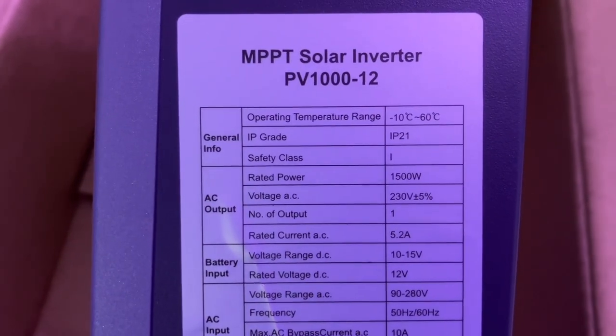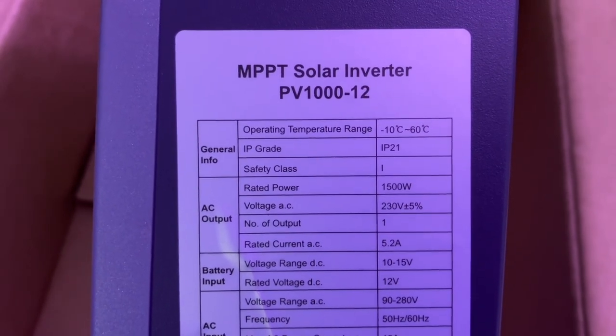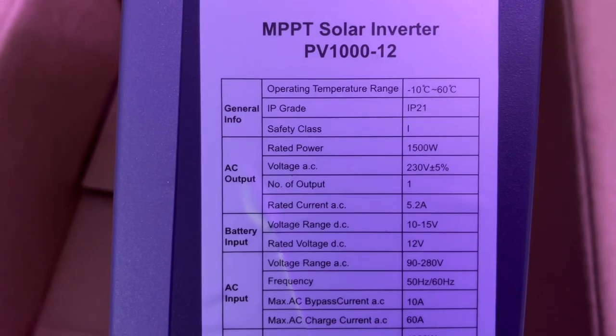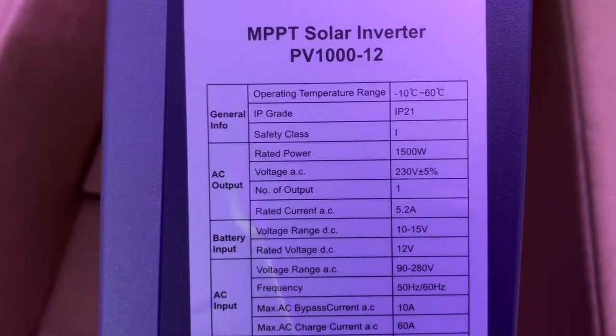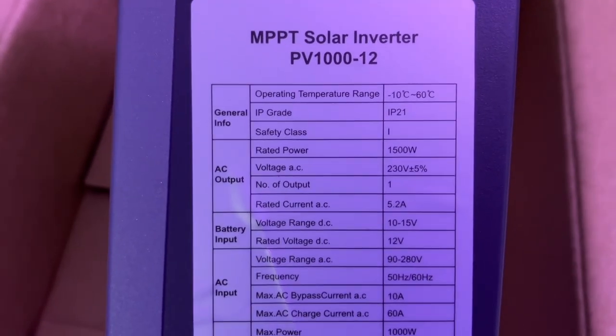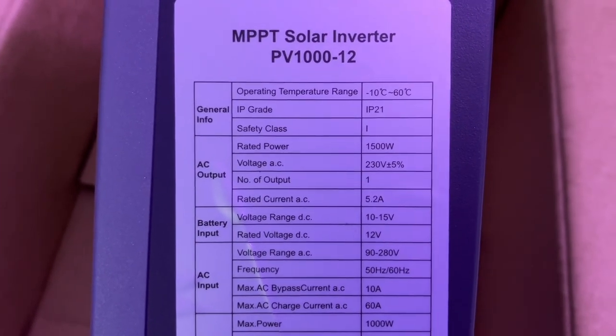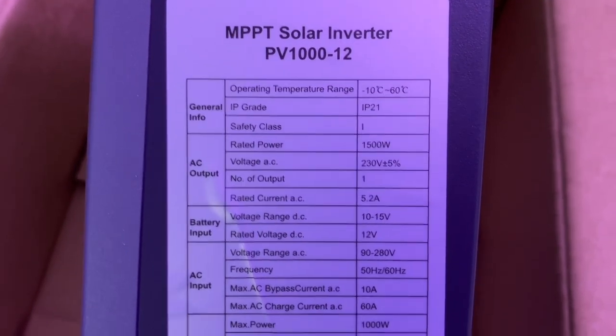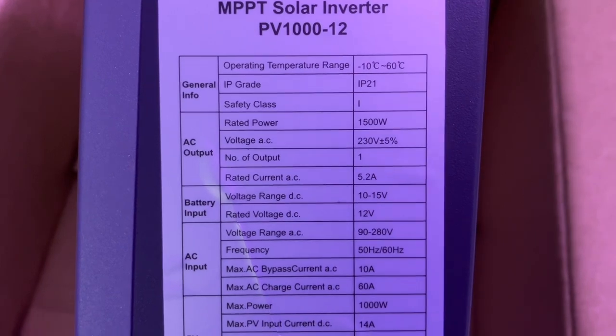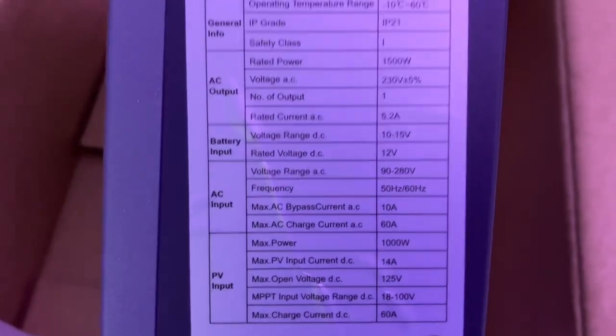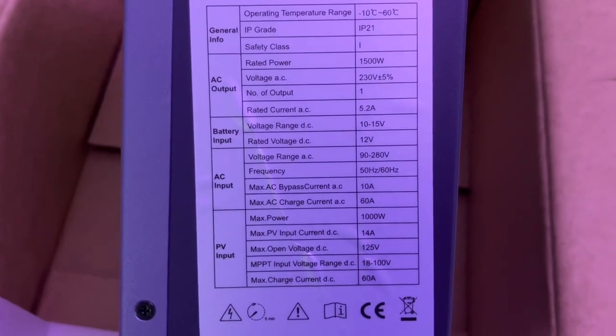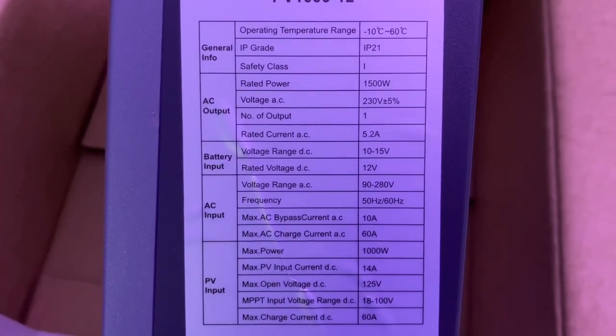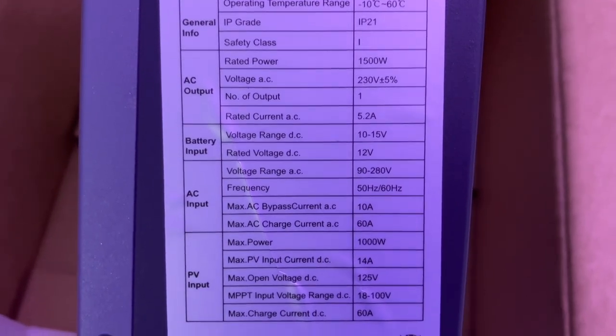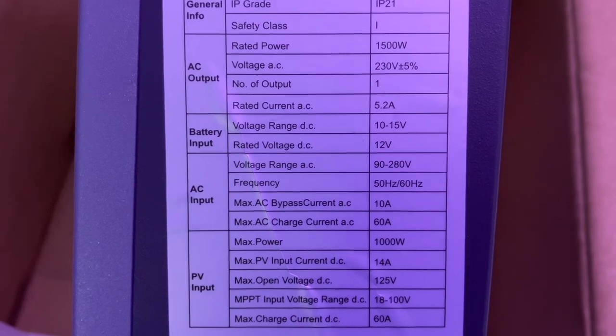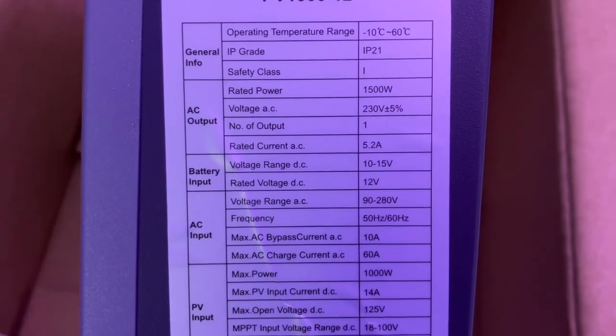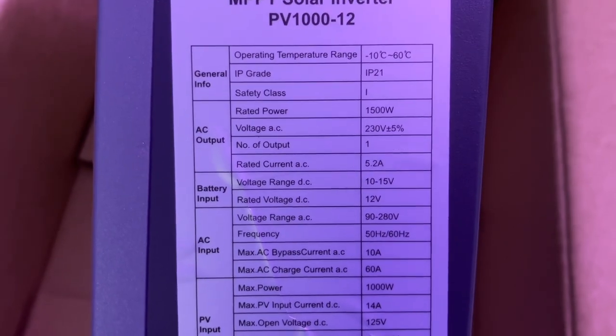Okay, so they said rated power is 1500 watts, and you can see something interesting here. They said rated current is 5.2. The accurate power for this is 230 times 5.2, which gives us 1200 watts. So this inverter is only 1200 watts and 1500VA.